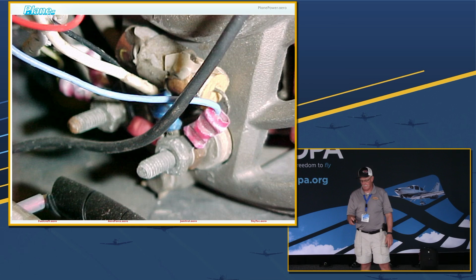On some alternators you have to pull the brush block assembly out, every 500 hours. This one has a bottom nut that got loosened, so the carriage bolt dropped down, and when it got pulled back up it didn't get pulled into its little slot. So it's just sitting there, and the shunt lead is bouncing around on there. That gives you an intermittent alternator.